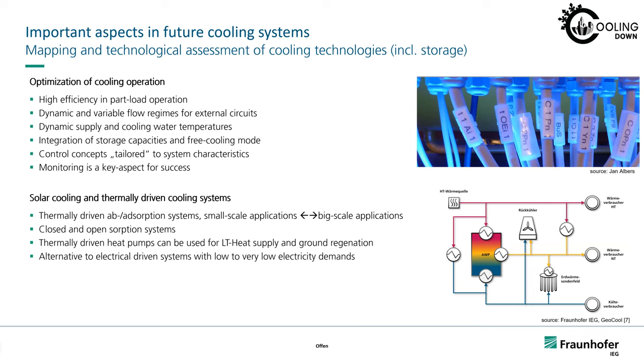Furthermore, one important thing we usually neglect is the optimization of a running system. Optimizing the cooling operation can lead to high efficiency, especially given the many part-load conditions cooling systems have. We're talking about dynamic and variable flow regimes for external circuits, dynamic supply and cooling water temperatures, and integrating storage capacities and free cooling mode so that control concepts become tailored to the system characteristics. To achieve this, monitoring and knowledge of system operation is key.